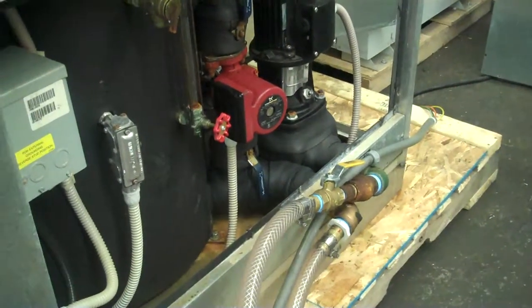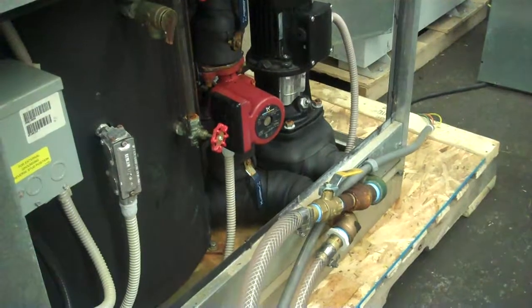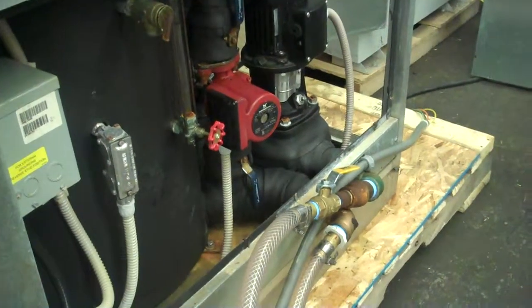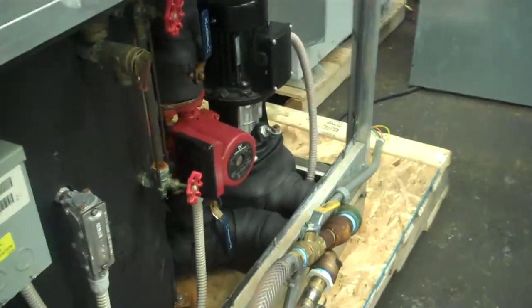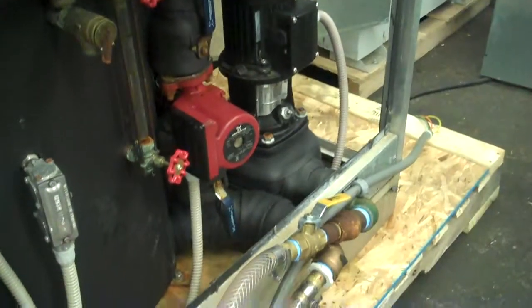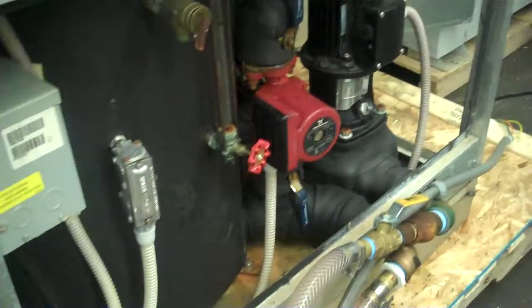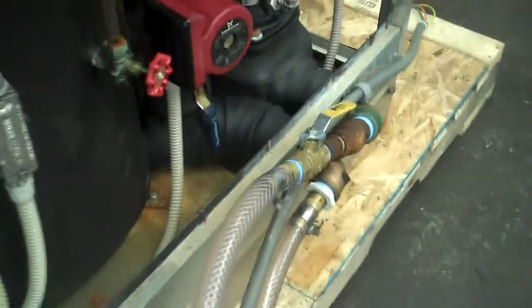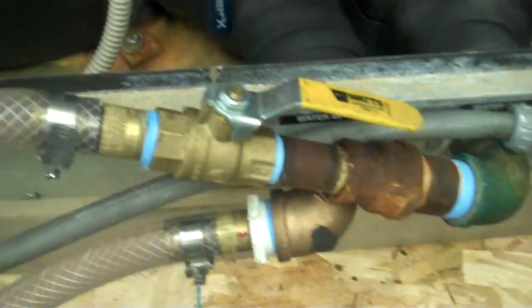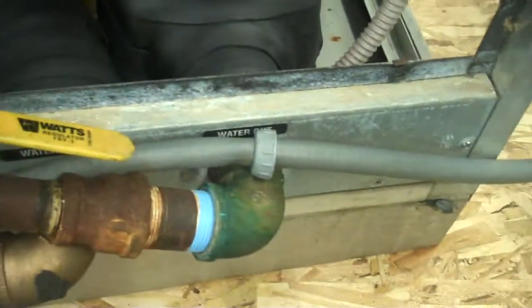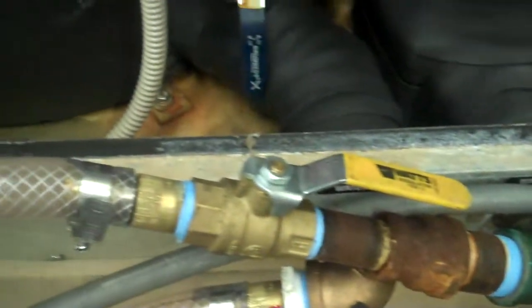We're not too worried about how we're running the test right now because we're going to keep the pump running. But for those type of really super low temperatures like we're dealing with now, a 50% glycol solution really is suggested. In a little bit here, we'll probably start seeing some frost accumulating on some of the fittings. It'll take a little bit.